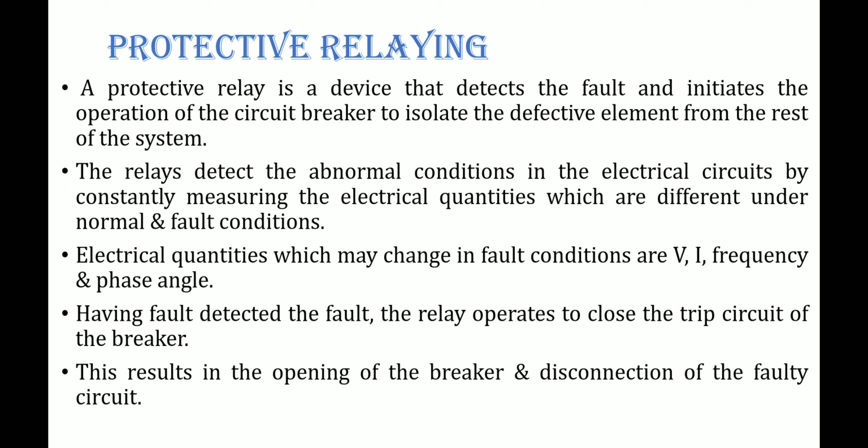Whenever changes occur in these electrical quantities, they can be detected with the help of these relays. Getting my point? Once the fault is detected, the relay closes the contacts of the circuit breaker and trips the breaker circuit. This results in opening of the breaker and disconnects the faulty system from the rest of the healthy system. This component is also very important in substations.